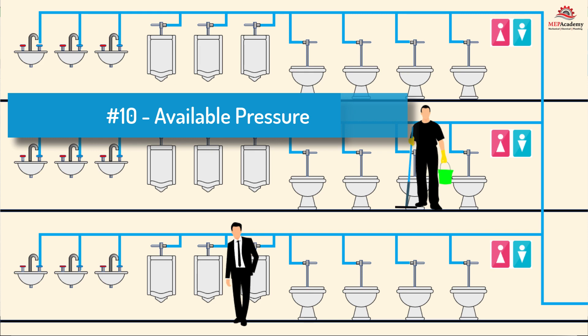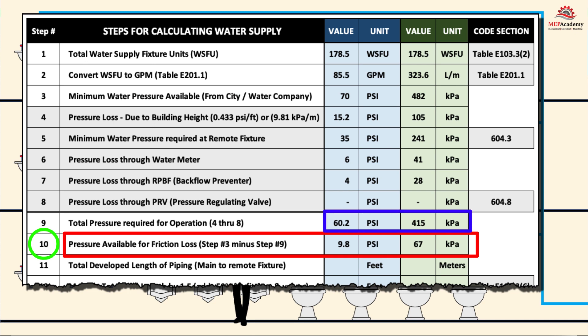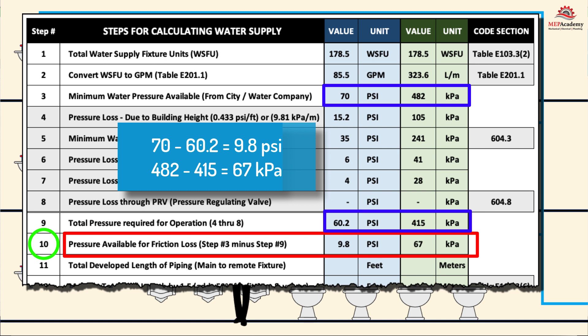Step 10: Pressure Available for Friction Loss. Subtract all the losses from Step 9 from the minimum available pressure in Step 3. If the available pressure is 70 PSI or 482 kPa, the calculation is: 70 PSI − 60.2 PSI = 9.8 PSI, or 482 kPa − 415 kPa = 67 kPa. This is the amount of pressure remaining to overcome friction losses in the piping system.